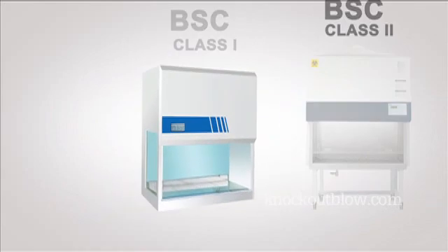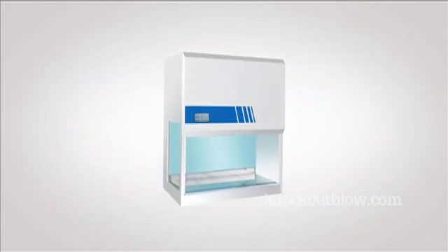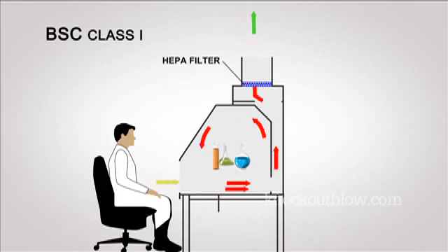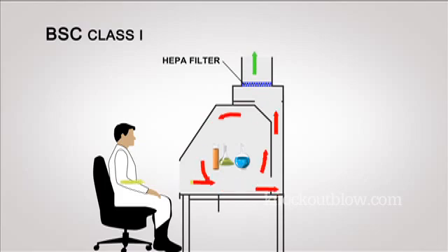Class 1 BSC: Class 1 cabinets have exhaust air that passes through the HEPA filter. They offer personnel and environmental protection from biological agents but do not offer product protection.